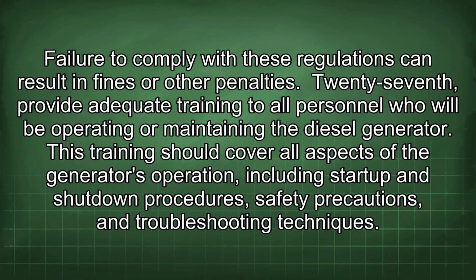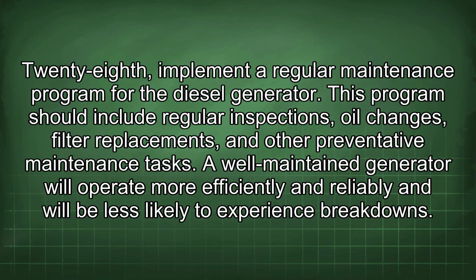27th. Provide adequate training to all personnel who will be operating or maintaining the diesel generator. This training should cover all aspects of the generator's operation, including startup and shutdown procedures, safety precautions, and troubleshooting techniques. 28th. Implement a regular maintenance program for the diesel generator. This program should include regular inspections, oil changes, filter replacements, and other preventative maintenance tasks. A well-maintained generator will operate more efficiently and reliably and will be less likely to experience breakdowns.